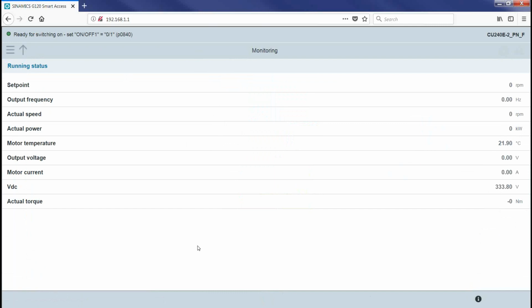Monitoring again. I'll set my speed pot to a level, and you'll be able to see it's running in reverse. I'll turn on the reverse input. So now it reverses. So it's just a quick way to come in and do monitoring of the motor, of the drive: speed, frequency, temperature, voltage.